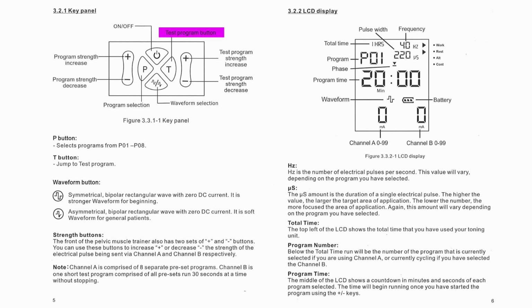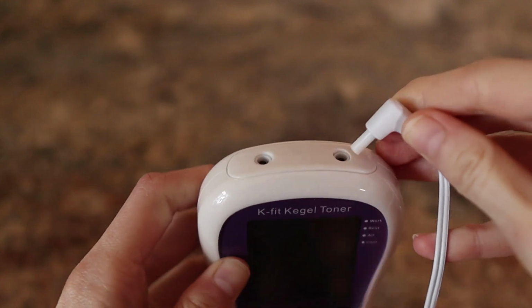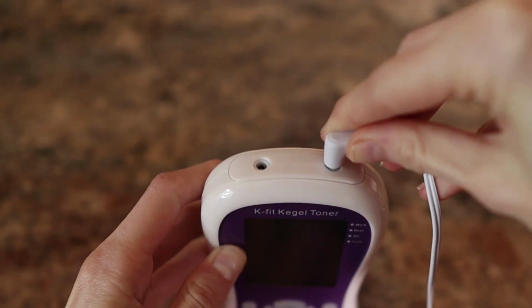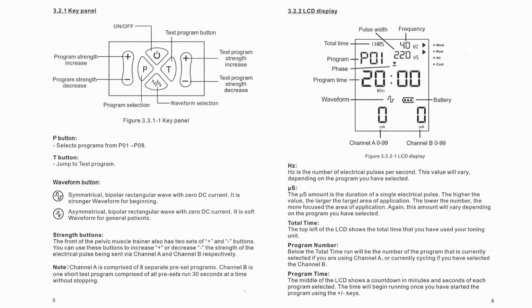The T button stands for test, and it's used to see how all of the programs feel. If you want to test each program before choosing the one that feels best to you, then you will use this side. To use the test side, you will plug your probe into the right port at the top of your toning unit called Channel B in your guide. Press the T button and then use the plus and minus buttons on the right to adjust the strength of the program. The test program runs for about 3 minutes, and you can watch on the screen as the programs change every 30 seconds or so.